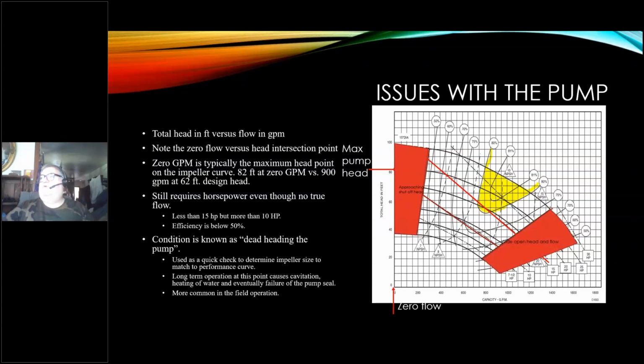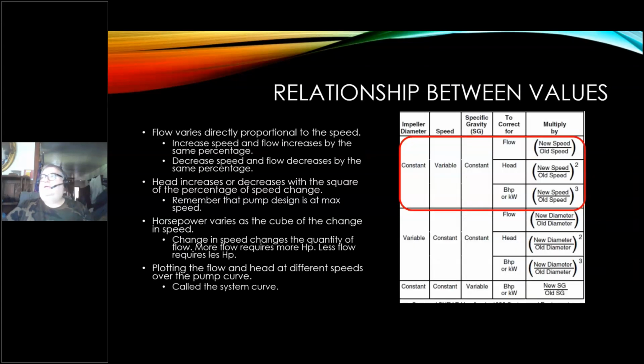These areas are kind of the danger zones. You're above and below where it's recommended to operate. You will not see these points on every curve. This curve just happens to have it. That's why I'm using it. Whether this pump actually exists in reality, I don't know. But back to our relationship.